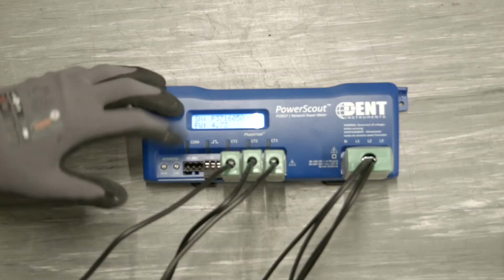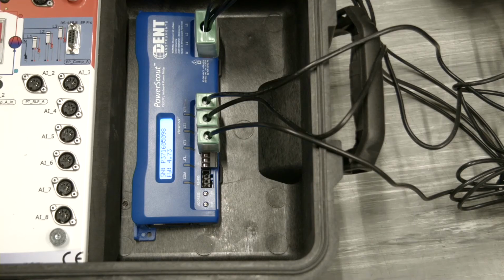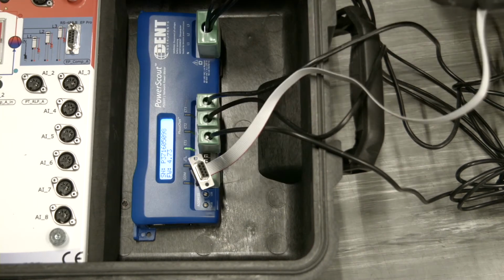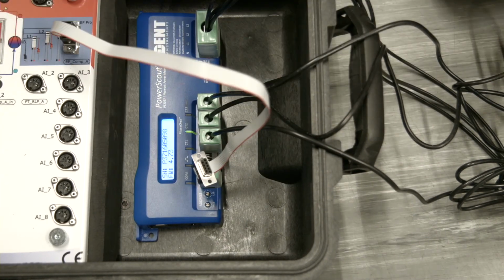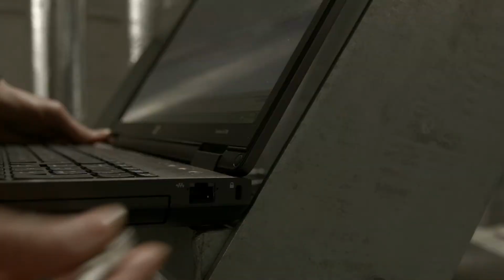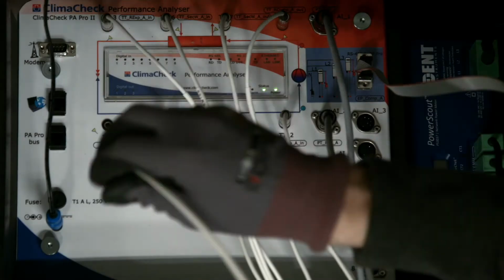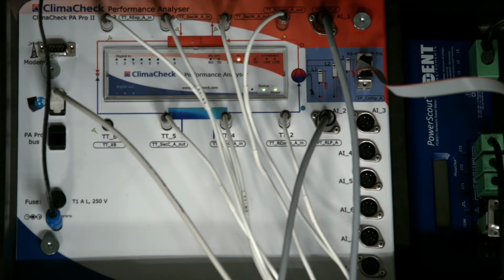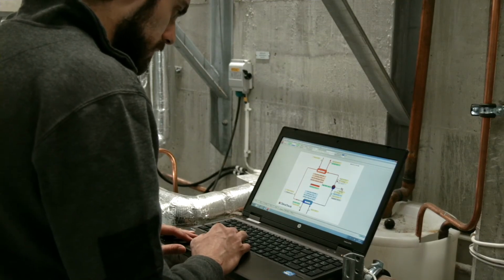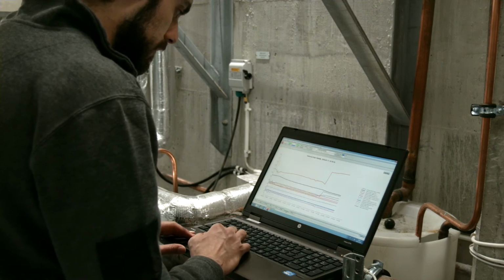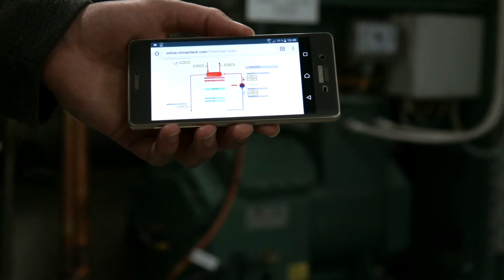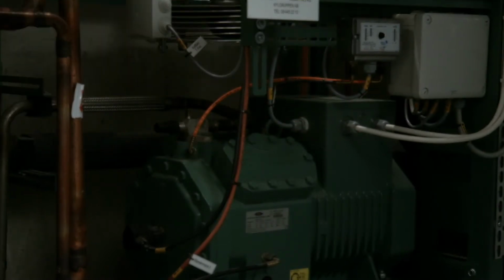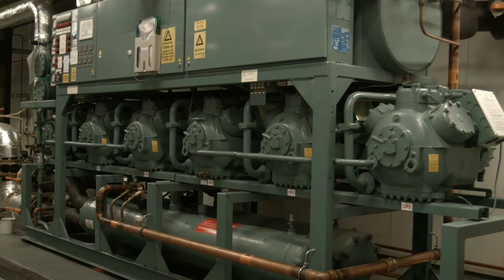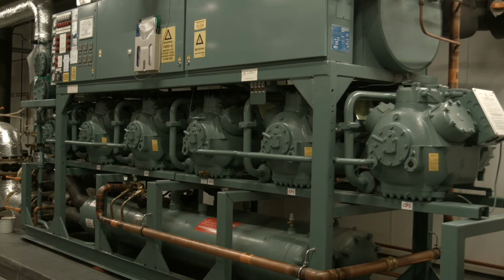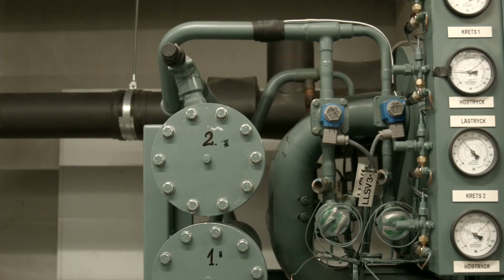The power meter then needs to be connected with a data cable to the ClimaCheck Performance Analyzer. LAN cable is connected to the computer from the analyzer. Fire up the ClimaCheck software and you're ready to go. You can see the system running either as a schematic, Excel view, graphical view, export to Excel. If it's connected to the web server, go online to your phone or a local computer and check that all the readings are being transmitted to our web server so you can leave the site knowing that everything is running correctly.